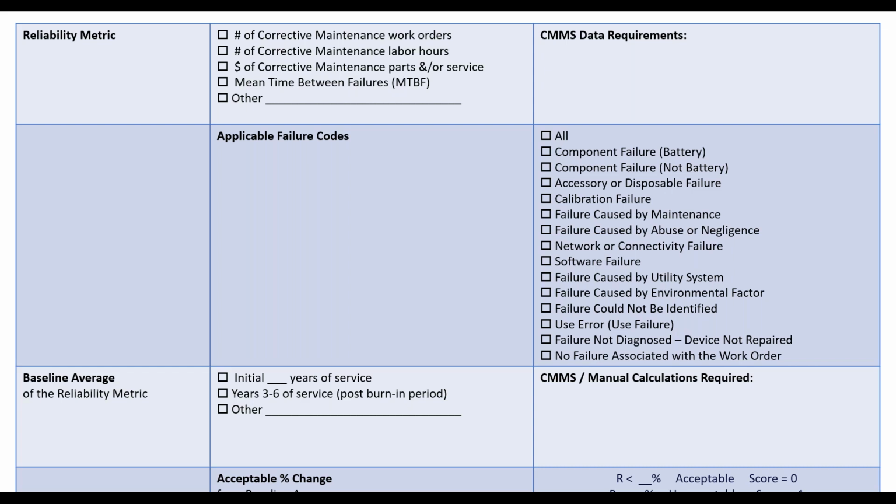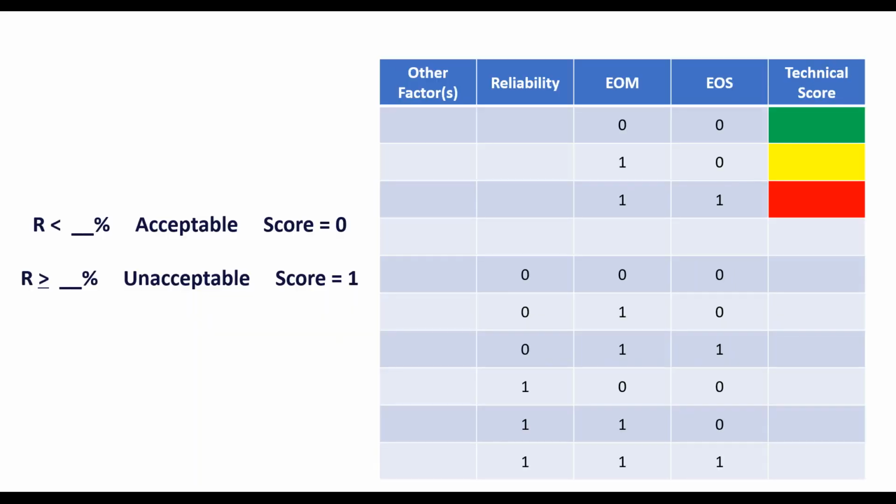Sure. So you raised a really interesting point. What we're doing here, remember, I said we're going to focus strictly like a laser on the technical aspects. You can do this very same activity from a financial perspective and a clinical perspective. And then do this sort of table where your top part is my technical score, my clinical score, my financial score, right? As HTM professionals, you're going to be responsible for the technical score. Nobody else can do that. Nobody else has the data.